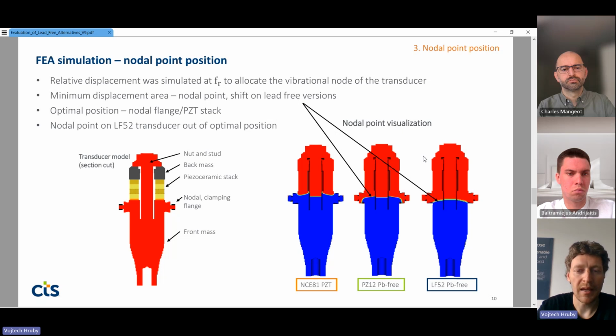And if we summarize, or state what the optimal position of the node is: typically this is at the nodal flange where the transducer is clamped, or at the position of the PZT stack, to give maximum performance of the transducer. So if we look at this ideal position, then we see that on the LF52 transducer, the nodal point is off the optimal position.